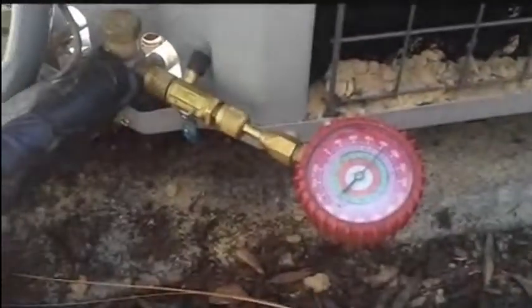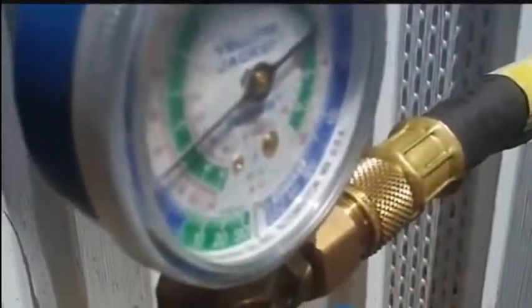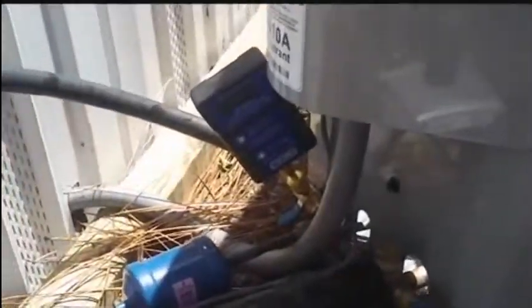So I'm going to take this off, let the nitrogen off, we'll hook up the vacuum pump and get it going. I got all our stuff set up. I got the 1/2-inch hoses hooked up to either side, valve core removers. Got a little bit different vacuum gauge on there this time. The S-mans weren't cutting it, so they got fired. And we got it shut off. We're about to turn it on and get to it.